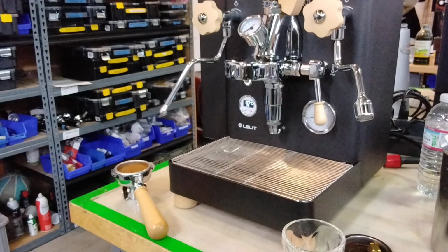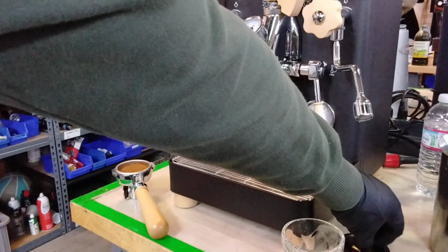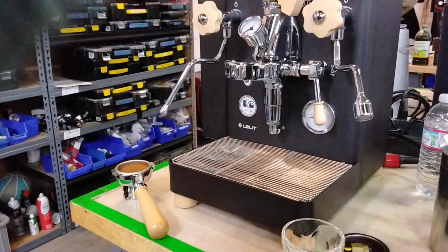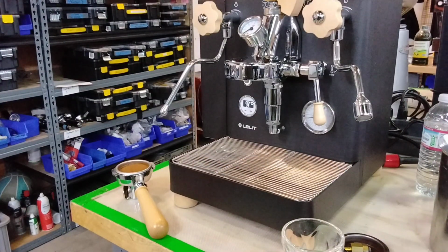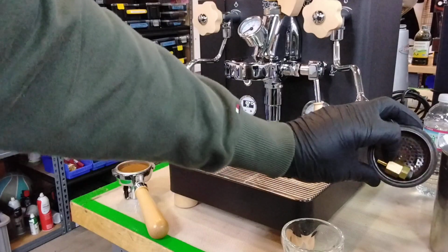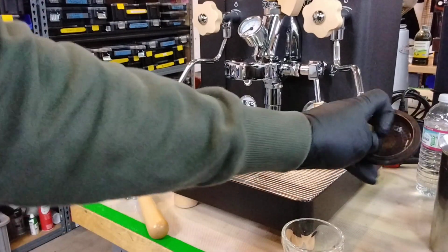When I tested it, I found the machine needs a tune-up. The vacuum release valve was also leaking, so I replaced it, cleaned and resealed the water level sensor probe, and replaced the shower screen and the group head gasket. These two.